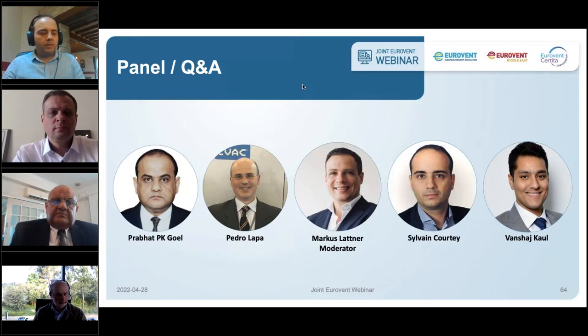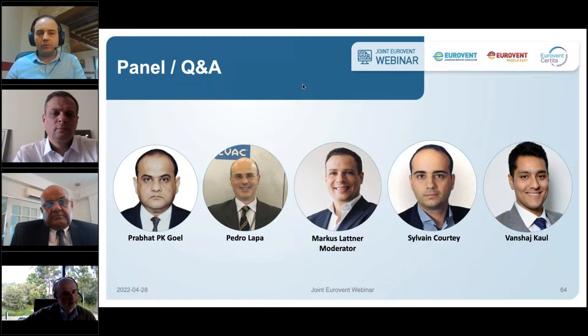Yes, basically we are limited because we are using tests in independent laboratories. If we want to certify a unit, we have to be able to test this unit in independent labs. So we have some limitations, but basically we can test the main ranges you can have on the market, which is from 5,000 to 15,000 cubic meters per hour. These are certified. For higher rates, it's a bit more difficult, but you can check with the manufacturers what is certified and what is not.